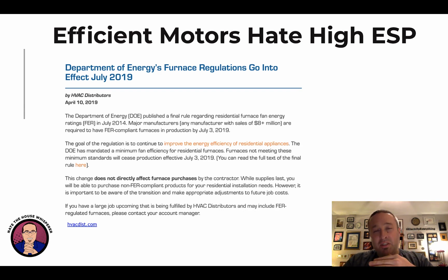The new ones are ECMs, which stands for electronically commutating motors. ECMs are much more like a European soccer player who's a prima donna—you touch them on the shoulder and they fall over writhing in pain, pretending there was a foul. They're very efficient and use a lot less power. Where a PSC will pull 500 to 1,000 watts all the time no matter what you do to it, an ECM on low will pull as few as 15 watts.